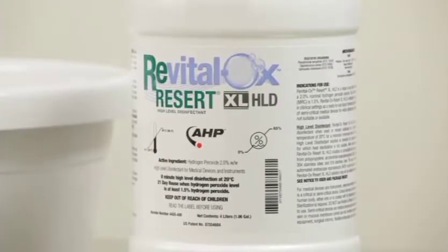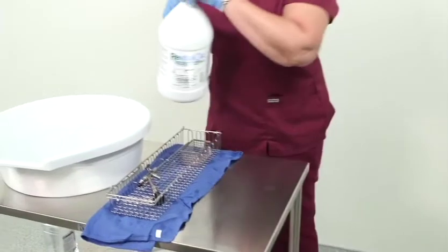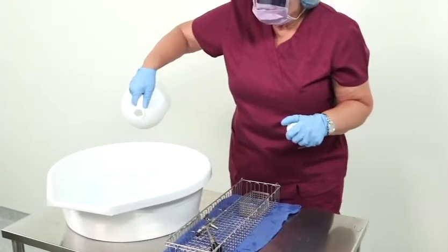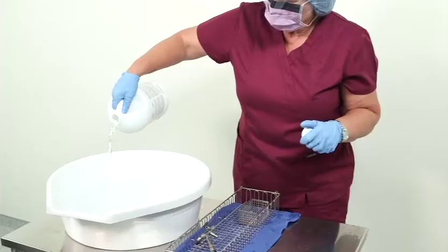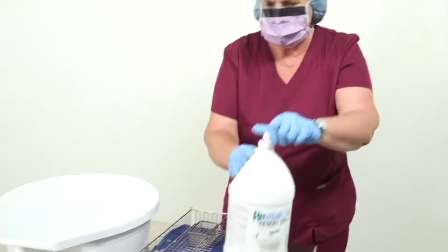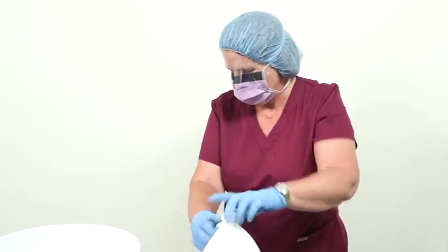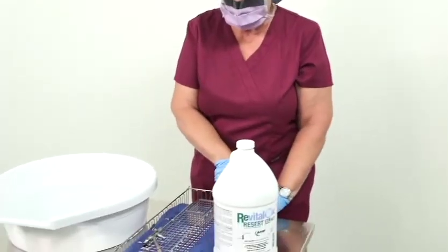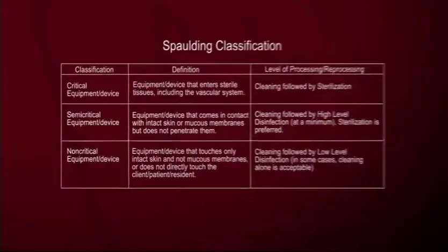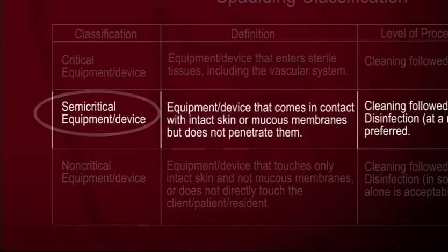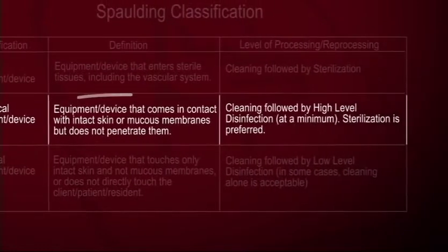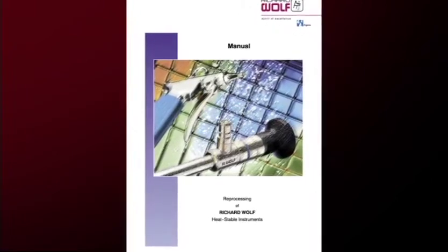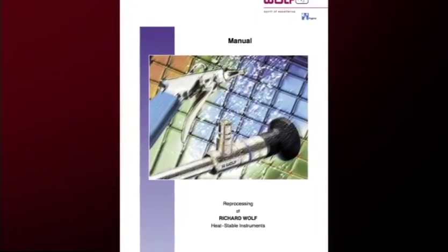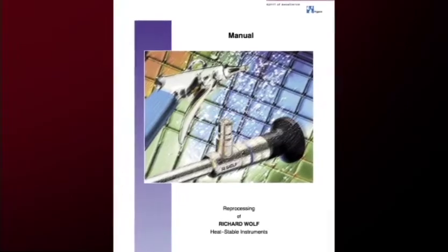A rigid endoscope may be validated for high-level disinfection using chemicals like glutaraldehyde, OPA, or liquid hydrogen peroxide. High-level disinfection may be used in the decontamination process or for immediate patient use. Always refer to your hospital's protocol and the Spaulding classification system when using a high-level disinfectant to process instruments for immediate use. Refer to the endoscope manufacturer's instruction manual to ensure the high-level disinfectant is validated to use with the scope.